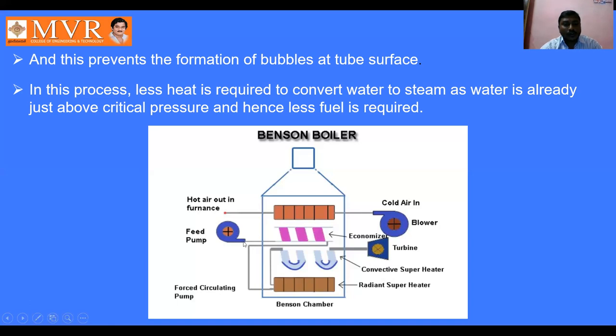The feed water is sent from the economizer into the radiant superheater, where some heating and reheating takes place. In the radiant superheater, the feed water is evaporated and converted into steam. From the radiant superheater, the steam enters into the convective superheater. From the convective superheater, it directly enters into the turbine. This is what about the Benson boiler diagram.